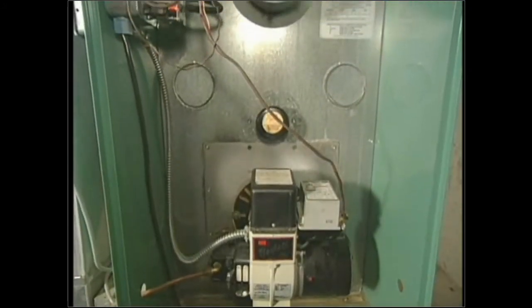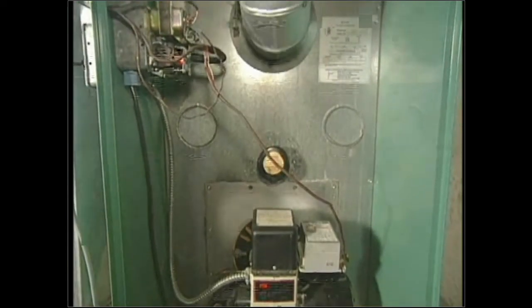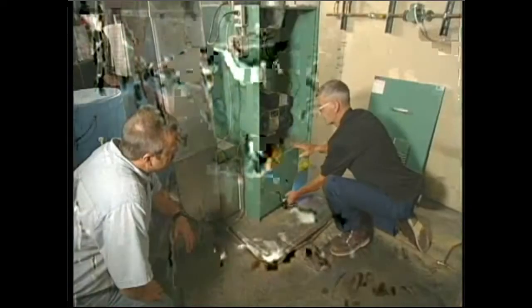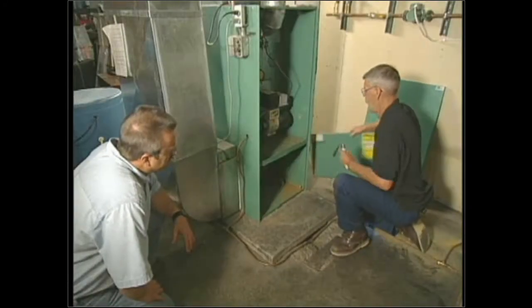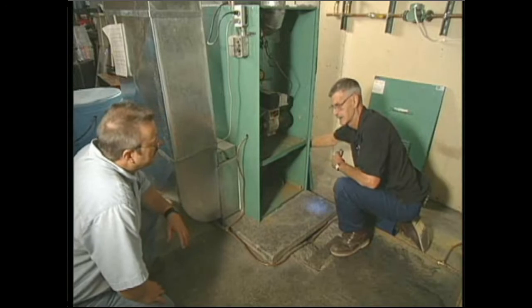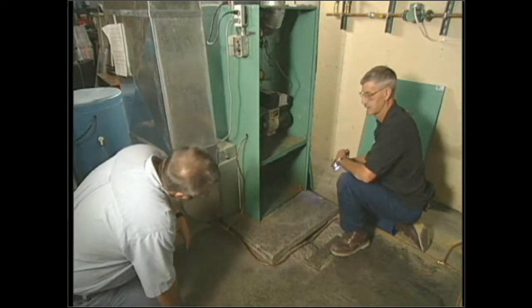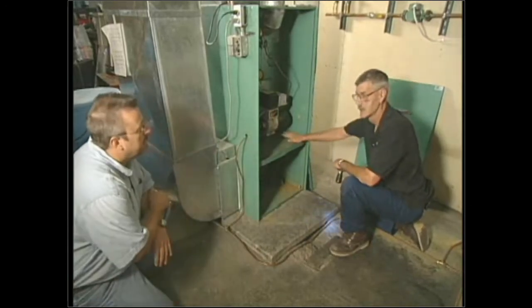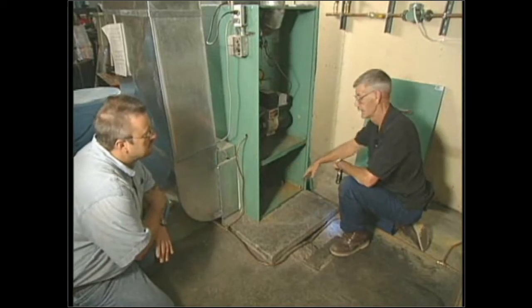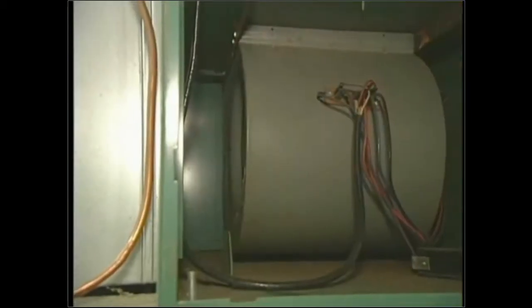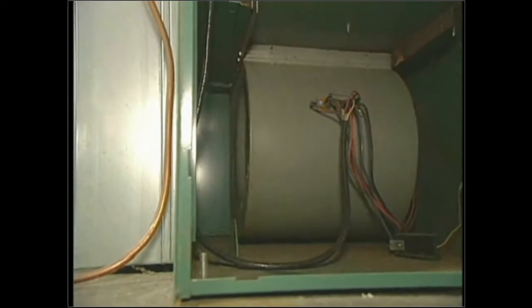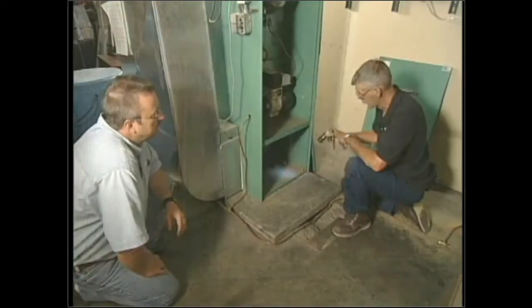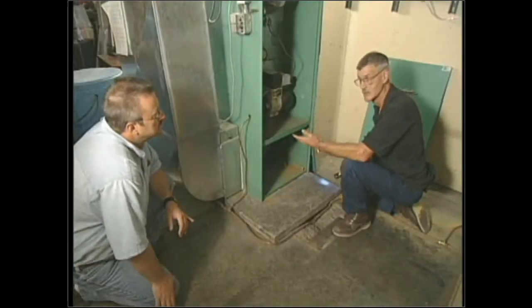I visually checked the deck, checked my flue, I looked at my connections, make sure my connections are tight. The next thing I'll do is pull this cover off. And now, this is a little bit different than when we did it on the gas, like on the 90 pluses, on the condensing furnaces. There should be no rust in here. If there is, it should be real light rust from just the moisture content from being in a basement. I'll visually inspect for dust and dirt, just as we did with the other furnaces.